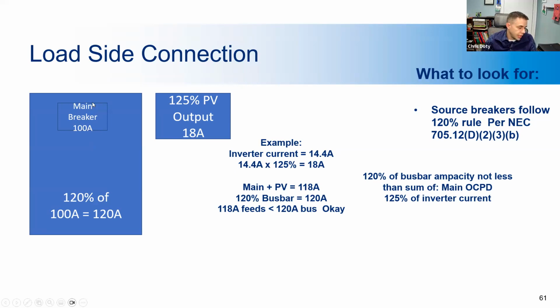In this example, you have a main breaker of 100 amps, a bus bar rating of 100 amps, and an inverter output current of 14.4 amps. You multiply that by 125%, and you get 18 amps. So the main plus the PV is 118 amps. 120% of the bus bar rating is 120 amps. So 118 is less than 120, so you are okay in this situation. That's an example calculation. Obviously, every system will be different, but it would follow similar rules.